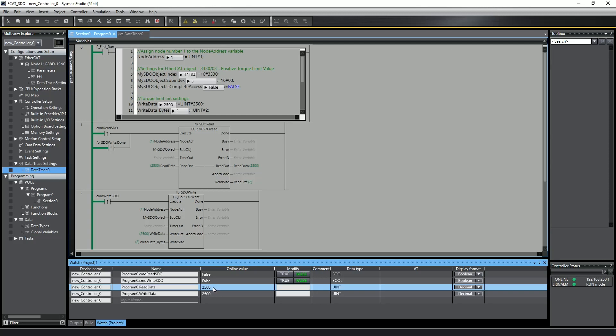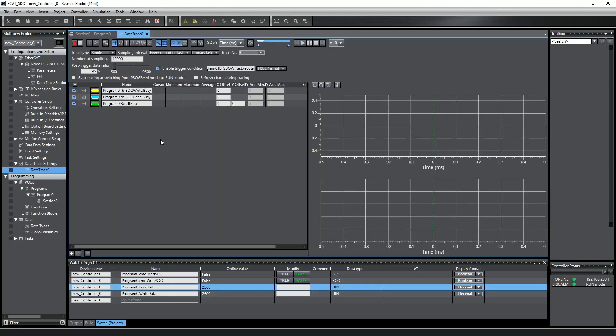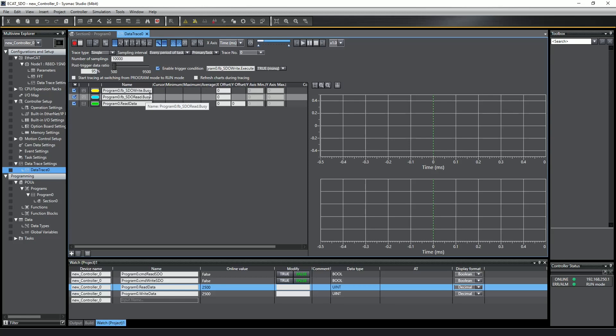SysMac Studio does have EtherCAT packet sniffers for troubleshooting, but another simple trick is to use the data trace tool. Here I have a data trace that's triggered by the execute bit of the write function block, and then I'm monitoring the busy bits of both the read and write function blocks and the read data variable.